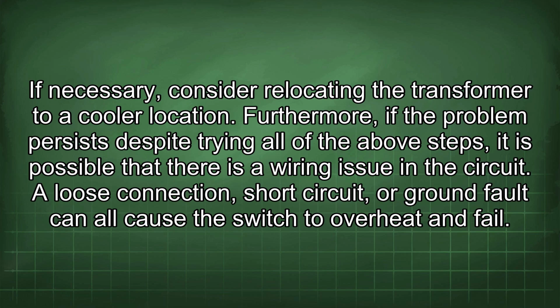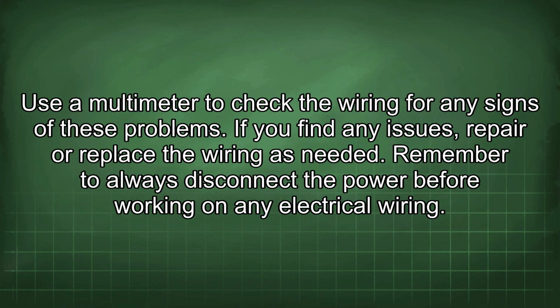Furthermore, if the problem persists despite trying all of the above steps, it is possible that there is a wiring issue in the circuit. A loose connection, short circuit, or ground fault can all cause the switch to overheat and fail. Use a multimeter to check the wiring for any signs of these problems. If you find any issues, repair or replace the wiring as needed.